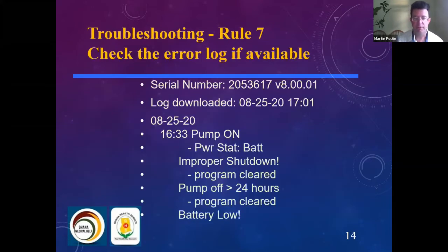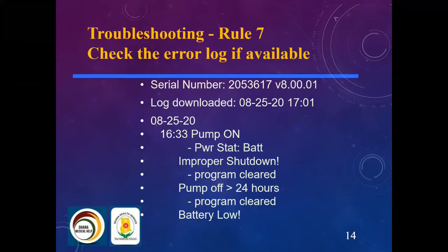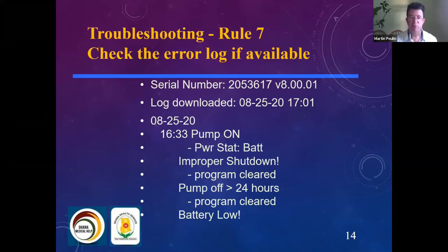Rule number 7, you should check the error log if it's available. Some equipment these days has event recorders and/or identifies an error code.